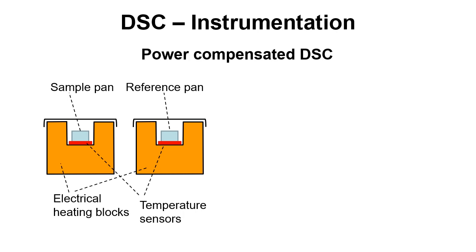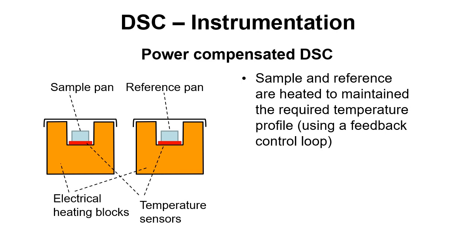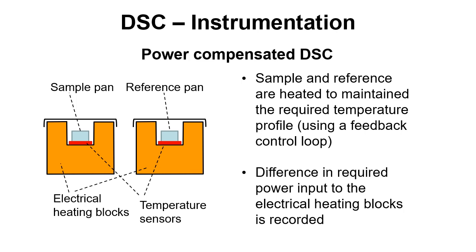For power compensated DSC, we have two separate heaters with a sample pan in one and a reference pan in the other. Both are heated to maintain the temperature profile that has been programmed in using a feedback control loop — we decide in the software what the temperature profile should be, and the heating blocks keep the sample pan and reference pan on those profiles. The difference in power required to heat the two blocks is recorded, and that gives us the result we then analyse.